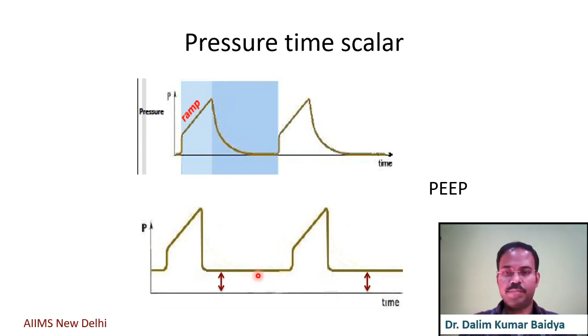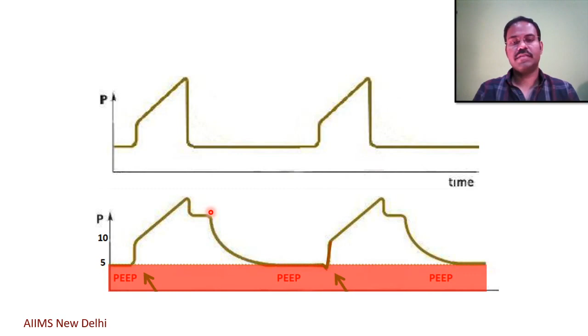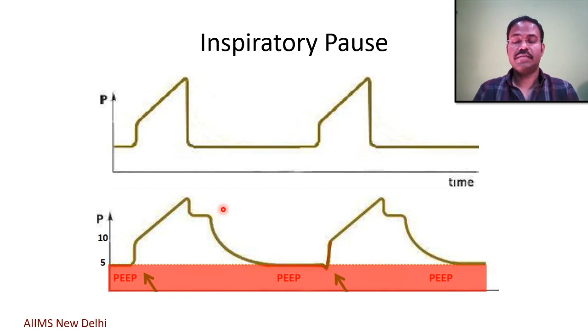Similarly, in this figure, if you observe, you will find that there is a difference in the pressure time scalar pattern in the figure above and the figure below. In the figure above, the peak inspiratory pressure is achieved at the end of inspiration and then the cycling occurs. However, in the figure below, after the peak inspiratory pressure, there will be a certain amount of time when an inspiratory pause has been applied and the pressure drops a little bit and is maintained at that level for some period of time, and then the cycling occurs. So this suggests that an inspiratory pause has been applied, and this is applied to measure the plateau pressure. We'll be discussing it in detail.